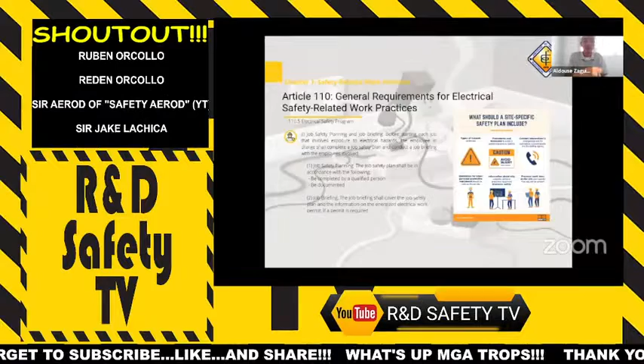This is good because you put this on the equipment being serviced, and also on the protective device or disconnecting device servicing the equipment. For the breaker, you'll tag it and put a padlock, so it's locked and disconnected by the serviceman, the worker, who tags it that this part is being serviced, so do not operate.